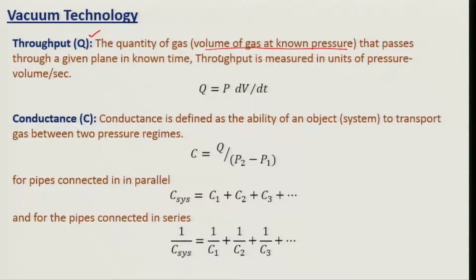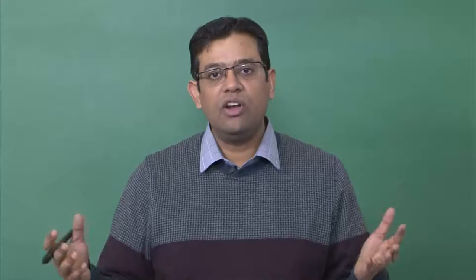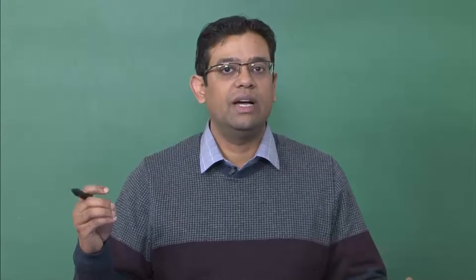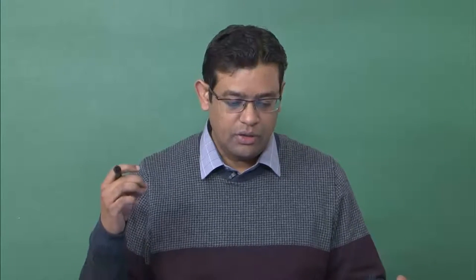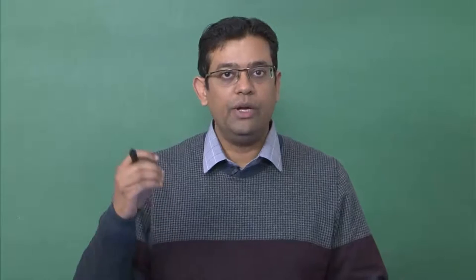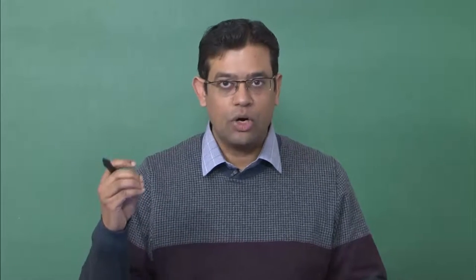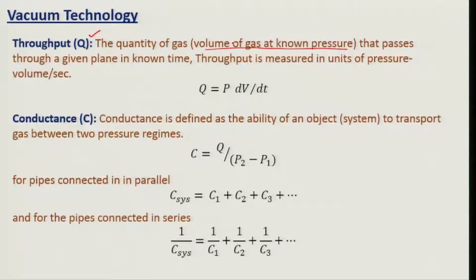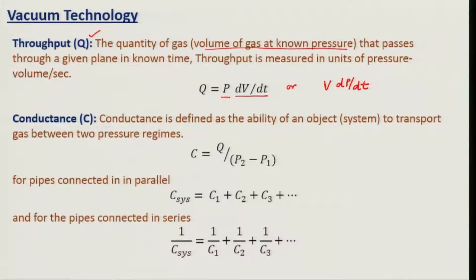Throughput is defined as volume of gas at known pressure because gas will occupy any volume you keep it in. So volume alone is not the exact measure of the quantity of gas — pressure times volume, P×V, is the quantity of gas. Throughput can be defined as Q = P × dV/dt at fixed pressure, or equivalently as V × dP/dt at constant volume.